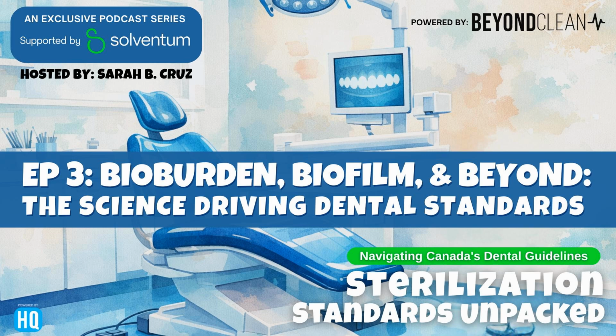It's time for Practice Defined, a quick pause to unpack a key term shaping dental sterilization and safety. Today, we'll talk about air removal and steam penetration tests. Commonly known as the Bowie-Dick test, this procedure confirms that pre-vacuum sterilizers can remove air efficiently and allow steam to fully penetrate porous loads. According to the CSA Z314, Reprocessing of reusable medical devices in healthcare settings, these tests must be performed at the start of each day the sterilizer is used. Whether completed with traditional test packs or electronic systems that record and store results, air removal verification is a daily baseline for safety and performance in every dental clinic. That's Practice Defined. Now that we're one term closer to excellence, let's jump back into today's episode.